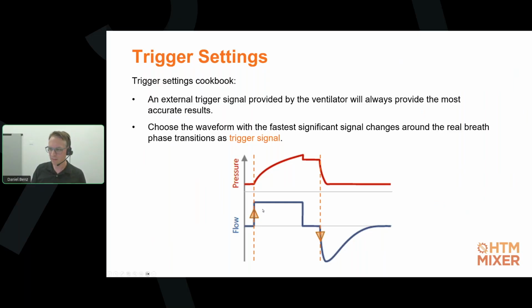In this example, we would choose the flow signal over the pressure signal because the flow signal has very significant and rapid changes when we have our actual real breath phase transitions. The pressure signal here is quite good at the end of the inspiration phase, but at the start of the inspiration phase, we call that a slow signal. It has a flatter waveform, a flatter curve. That means the pressure signal in this example is rising slowly and therefore not sufficient as a trigger signal.